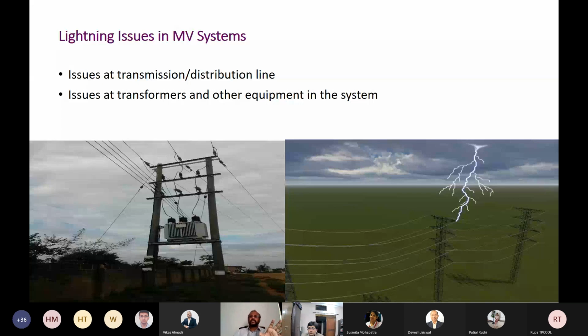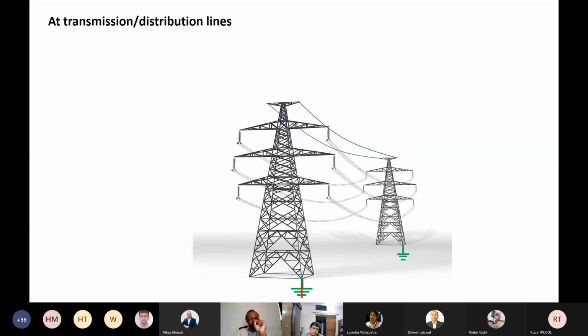Then in a transmission or distribution line, you have to pay attention to one important thing, because in most of the cases where I have done consultancies, people are very adamant on some prejudiced concepts. Say for an example, some people say that, okay, whatever the cost, you reduce the earth resistance of the tower footing. And some people say don't worry about the earth resistance of the tower footing, or TFR, but we are worried about the backflashover, and so go for lightning protection systems at the tower top.